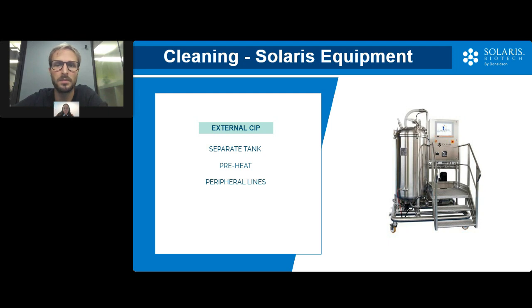Conductivity probes are often used to monitor the cleaning process, offering a way to monitor the ion concentration in the cleaning solution on the return line from the vessel. The peripheral lines, transfer lines, gas out, gas in, and so on can also be included. And usually what is done is to take into account TACT, so time, action, concentration, and temperature, to reach a reproducible cleaning cycle.